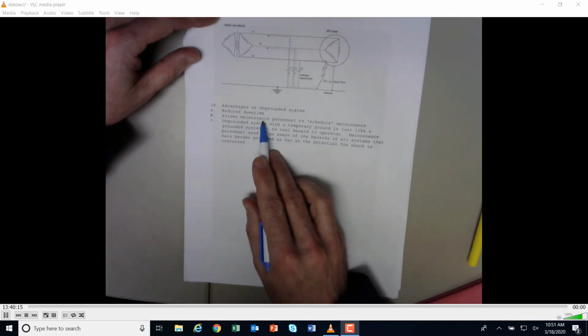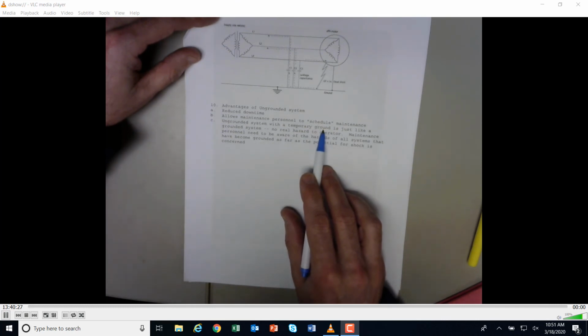There's a couple of other advantages of the ungrounded system. It is going to reduce the downtime, and it allows maintenance personnel to schedule maintenance, because you can leave it up as you work your way through some stuff. And remember, if you have an ungrounded system with a temporary ground, it's just like a grounded system. That's the best case where there's no real hazard to the operator, because any faults are going to be taken away by the ground. So whether it's a temporary ground or normal ground, you're going to blow a fuse if you have a problem. You're not going to be able to troubleshoot this on the fly.